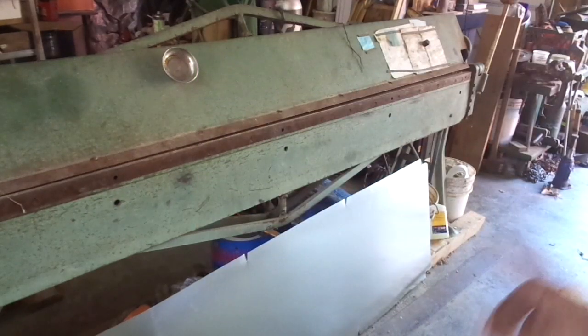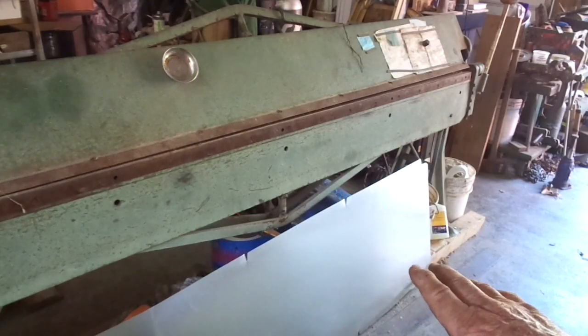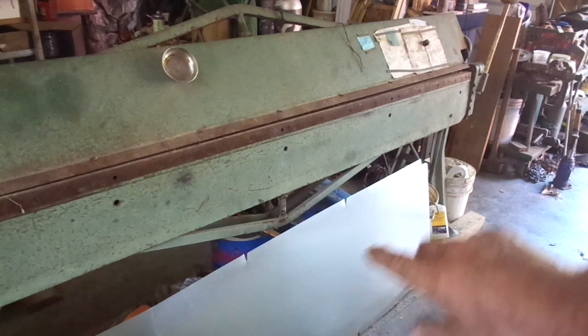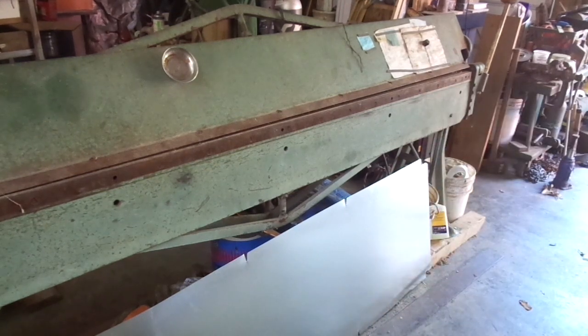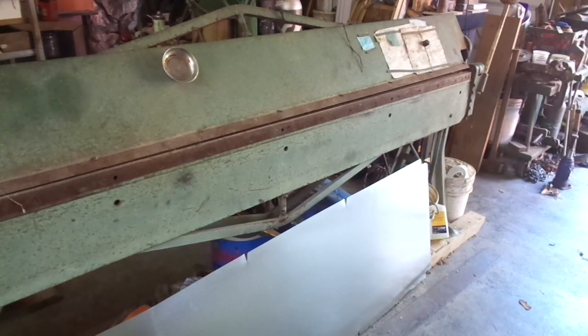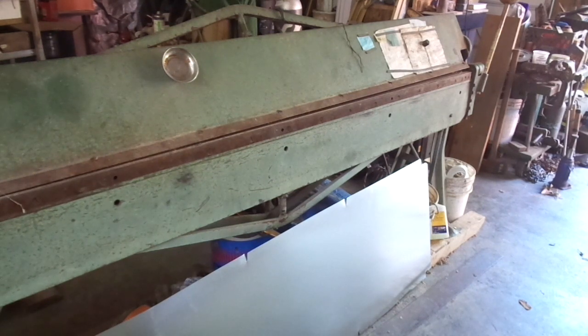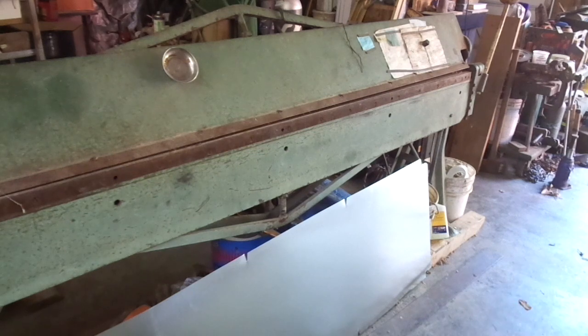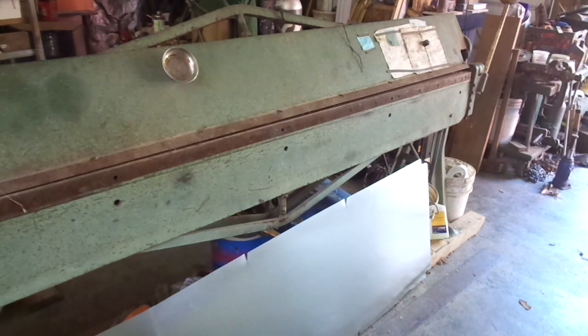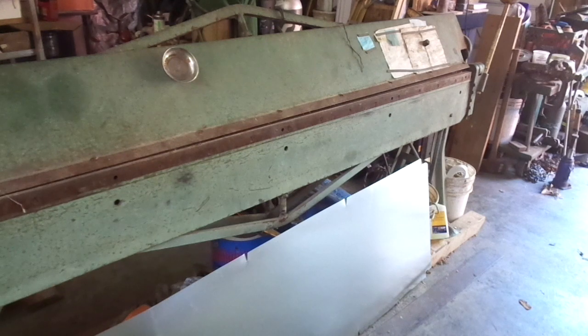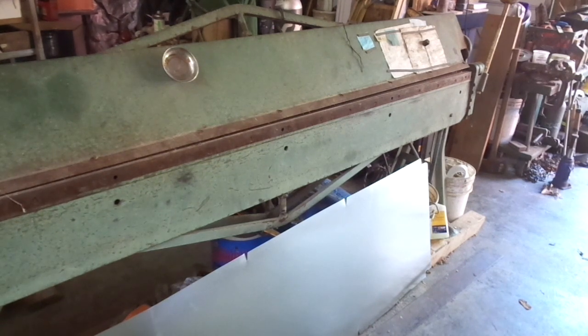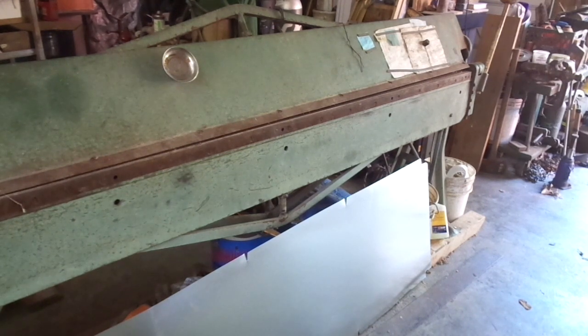I'm going to go ahead and notch that out. I should have done that beforehand so that there's no interference when the plugs get inserted in the wrapper. This is the Pittsburgh lock former machine. It's a lock former brand that manufactures a Pittsburgh lock. Sometimes in a shop that's as crowded as mine, you have to get a little creative with the longer pieces. Now, what I'm going to do now is I'm going to go ahead and cross-break the two sides and not the bottom of the horseshoe or the three-piece wrapper simply because if we cross-break them after we run them through the lock former machine, it'll smash the Pittsburgh locks down.